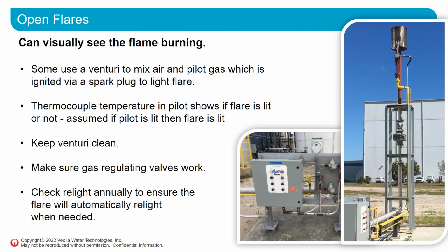So in terms of a remote indication from a SCADA, for example, it's important to keep the venturi clean so that your pilot is able to light the flare, and to make sure your gas regulating valves work. And you need to check that relight function annually so that your flare will relight when it's needed.